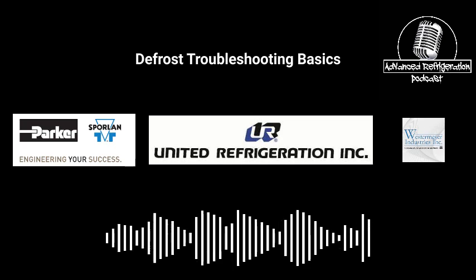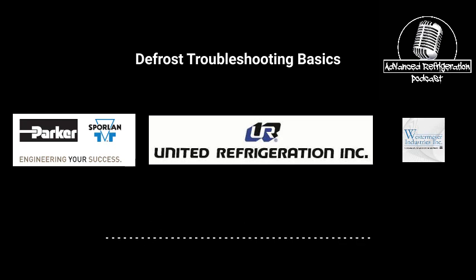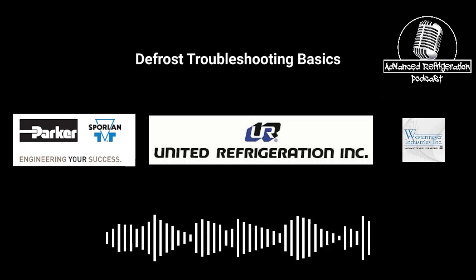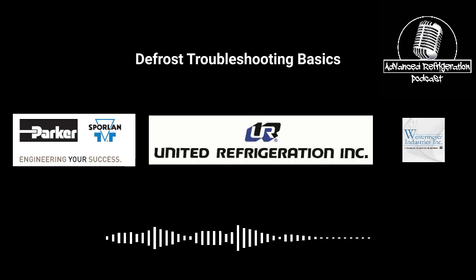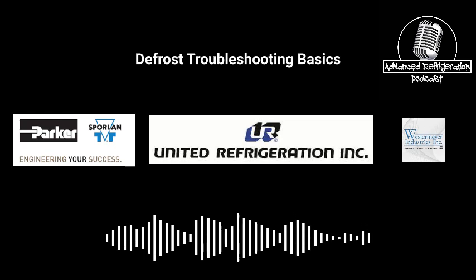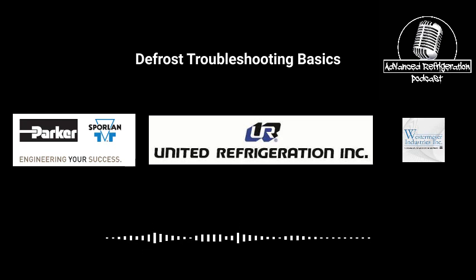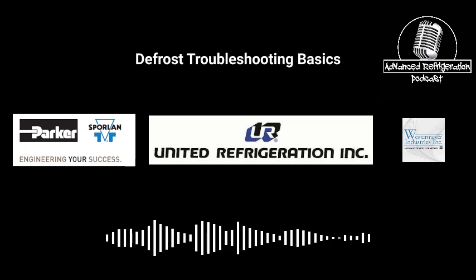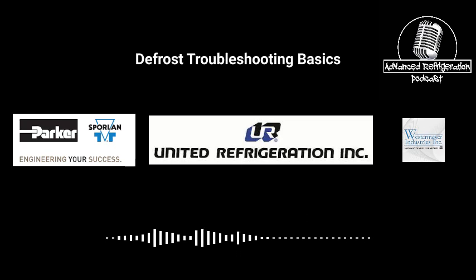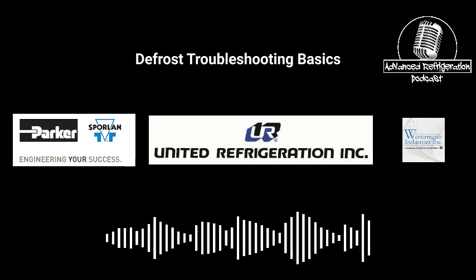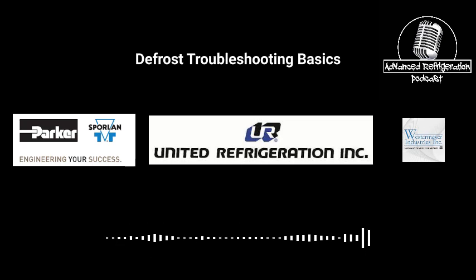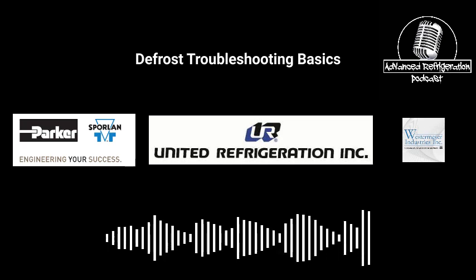Oh, wow. Well, one of the things you do have to make sure of when dealing with regular off-time defrost is that you're not getting any liquid generation slamming out at you. What I mean by that is, typically when you have off-time defrost, you'll either have a liquid line solenoid on a regular conventional case, or you will have a suction stop with a liquid line solenoid. It's basically just stopping the flow of refrigerant entirely. Sometimes with rack systems, you'll have a case where the liquid line solenoid is continually feeding because it's not fully seated. So it ends up filling the whole line from the liquid line solenoid all the way out into the evaporator, all the way back to the EPR at the rack. So you just have an abundant amount of liquid that gets stowed out there during defrost.